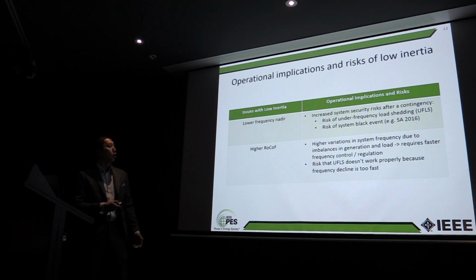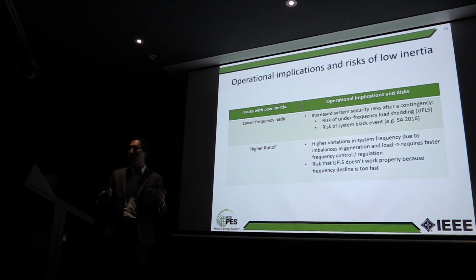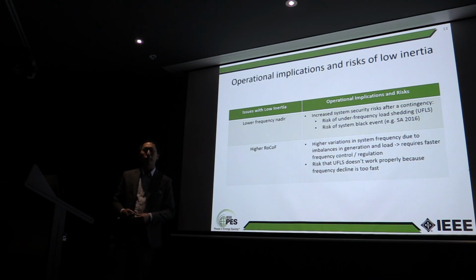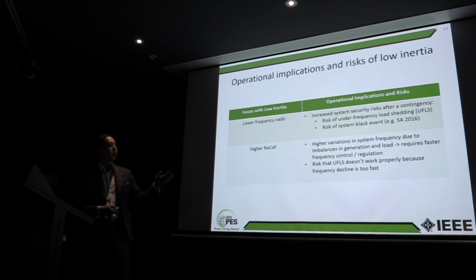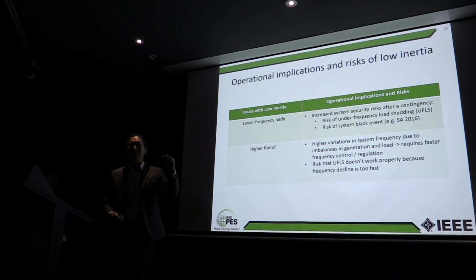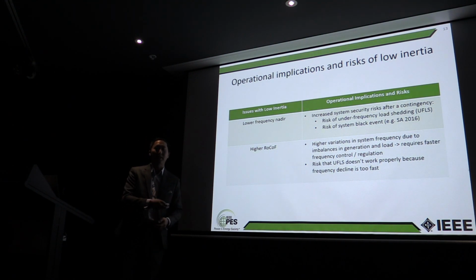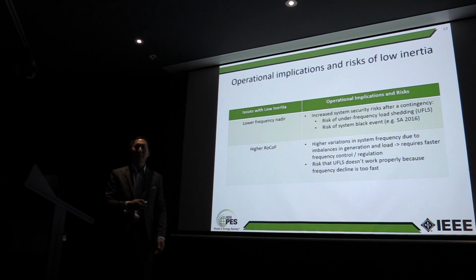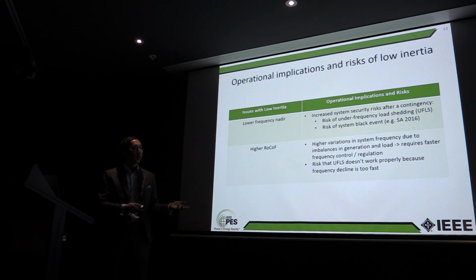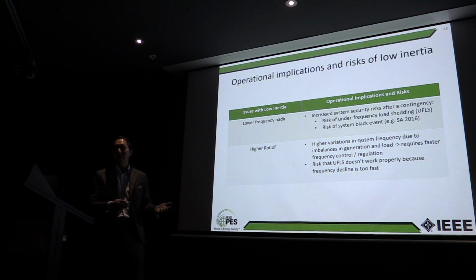Now, the risk of having a higher RoCoF is that obviously you have high variation in system frequency, so the system frequency is much more volatile. And so we would need faster frequency control and regulation of load following. There's also a risk that UFLS just don't work, because you're going so fast through the UFLS stages that as soon as you hit the first stage, you're already going through to the second and third stage. And so by the time the first stage knocks out some loads, you're already black. So that's another risk when your RoCoFs are too fast. Again, in South Australia, they had something like 3 hertz per second RoCoF. So the UFLS didn't work, put it that way. They have UFLS and they didn't work. So it went black.